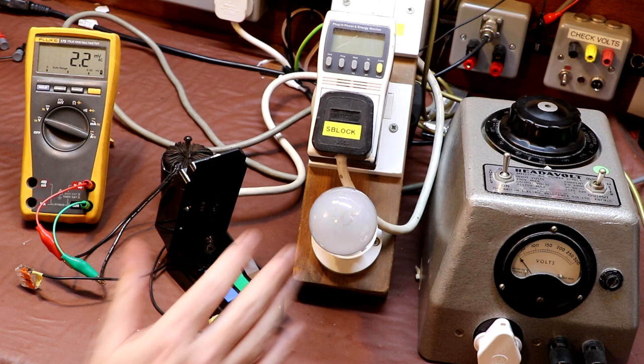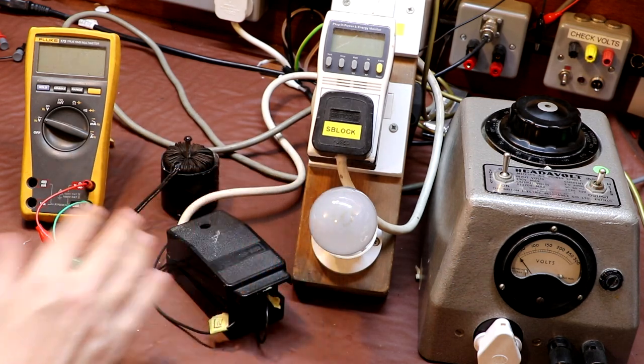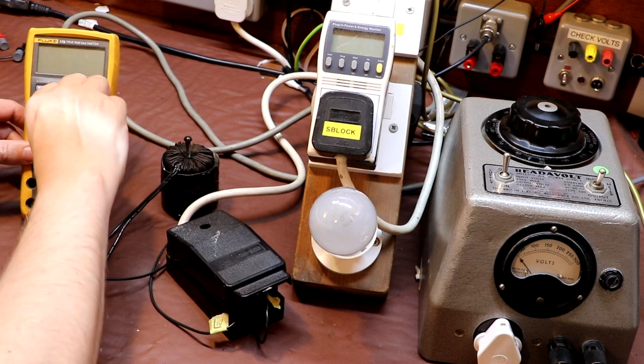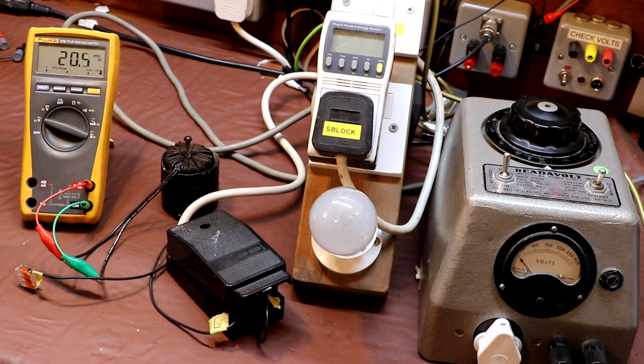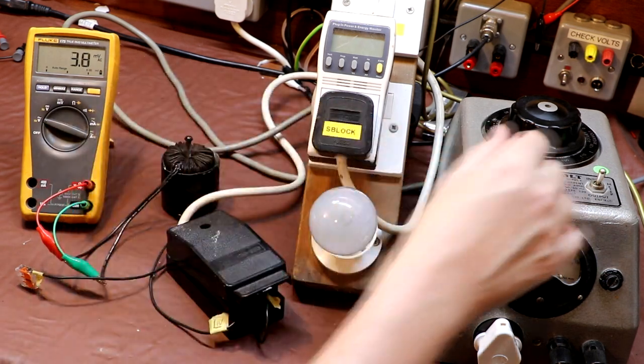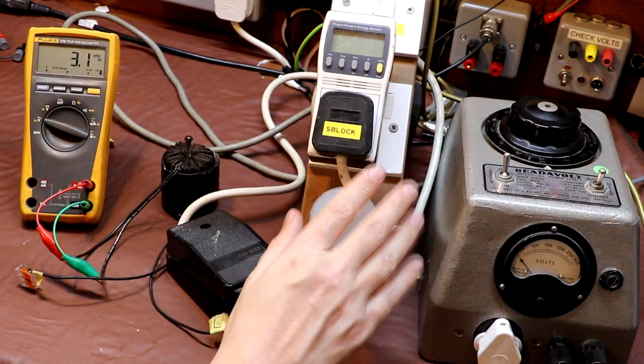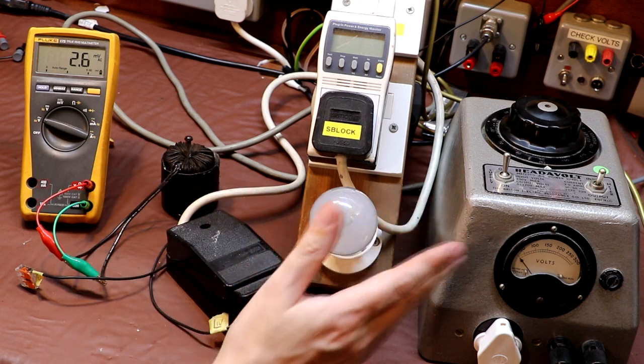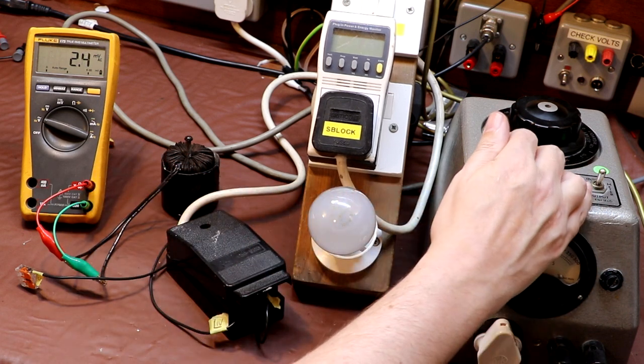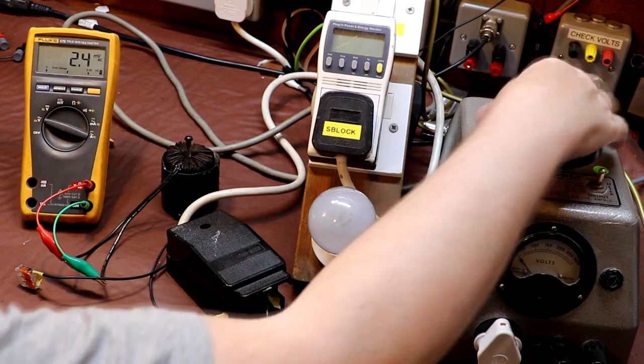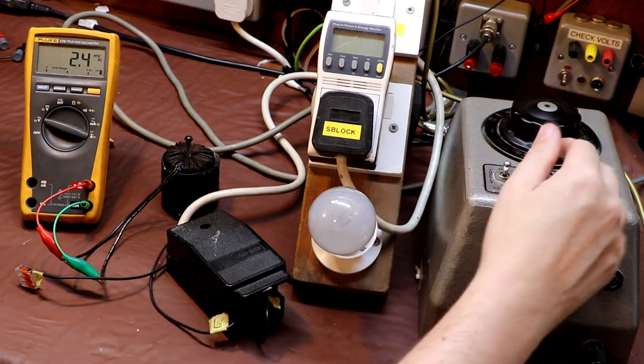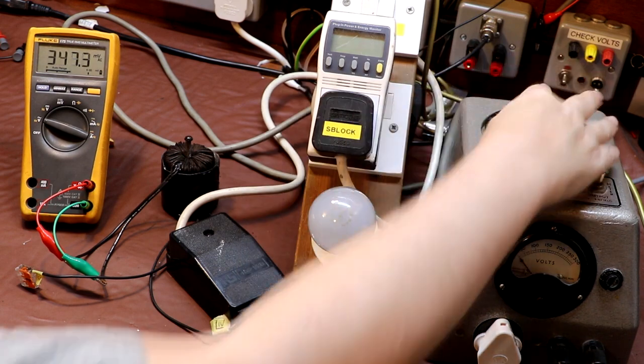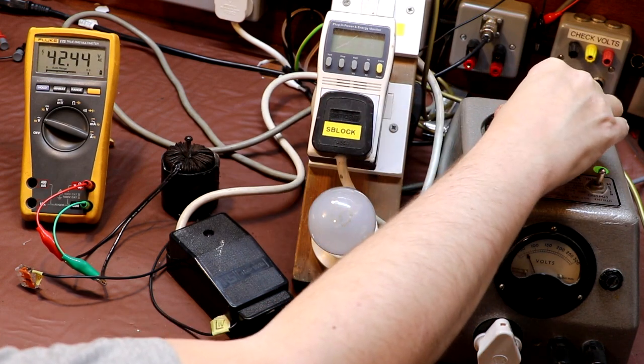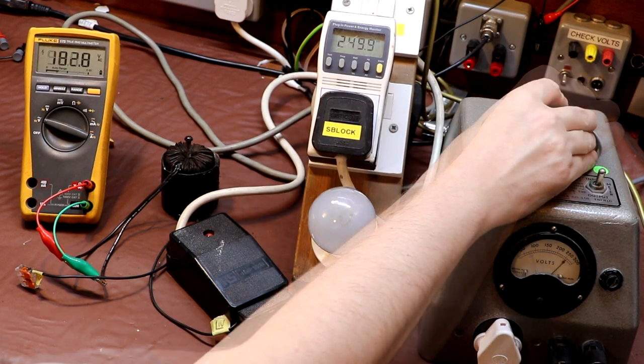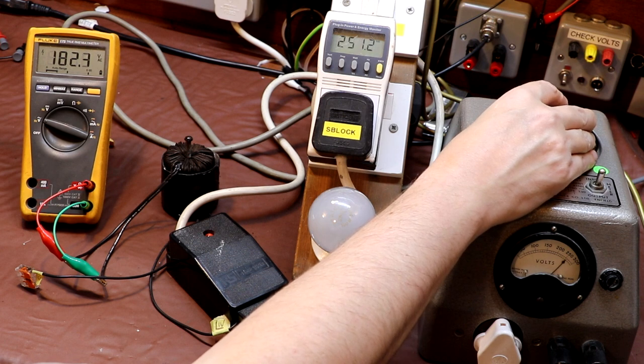So that's what we're going to do, and I guess we'll turn the power up relatively slowly, because this transformer's probably been asleep for the best part of, well, I suspect probably more than 80 years, could be even longer. So let's wake it up a little bit gradually. We've got the lamp limiter on, so if anything goes catastrophically wrong, the lamp should come on. So switch power on, turn the variac down. See if I can get it dead on 250.